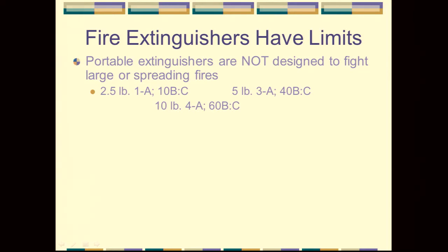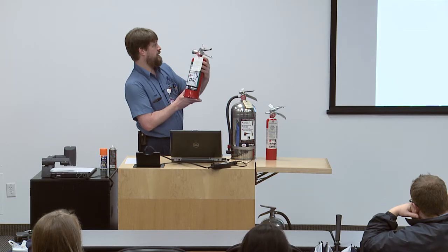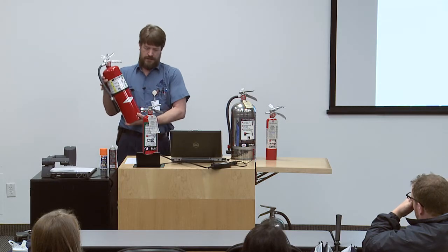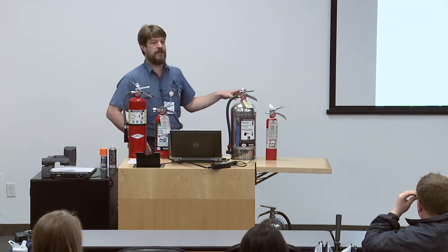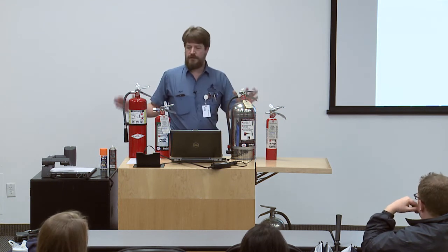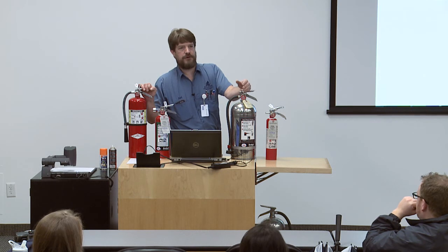There's your 2.5, 1A, 10BC. We'll talk about those numbers in a minute. Your 5-pounder, 3A, 40BC, and your 10-pounder, 4A, 60BC. Like I said, the C there doesn't really give a designation of anything other than it's okay to use on, or safe to use on electrical equipment without killing you. It's not that it's good for the electrical equipment. All of these ABC chems will eat through metal, so don't shoot them off near your car. If you do, take your car to the car wash.